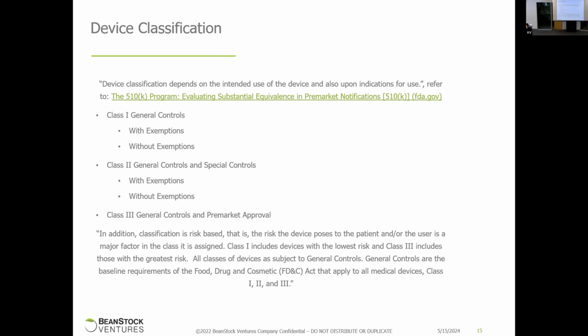It's exempt, but you still need to register with the FDA and you still need to show some level of design controls. It is considered exempt, which means it does not need to go through a clearance or approval process with the FDA, but the FDA can come and audit you if they choose to, and you do have to make sure you're managing complaints and you're instituting proper and solid design controls.